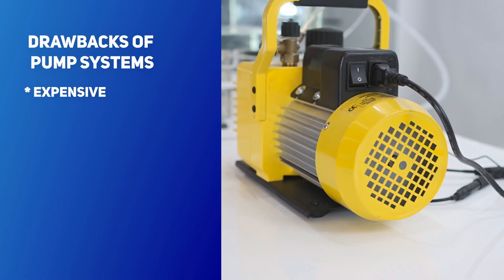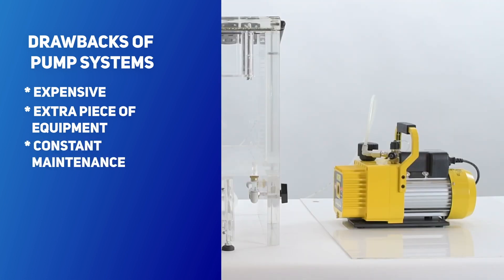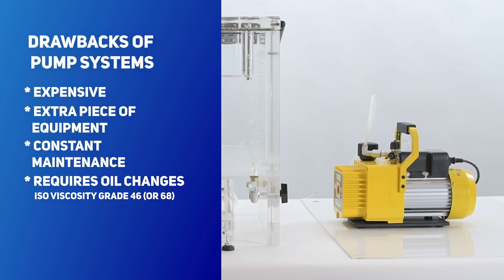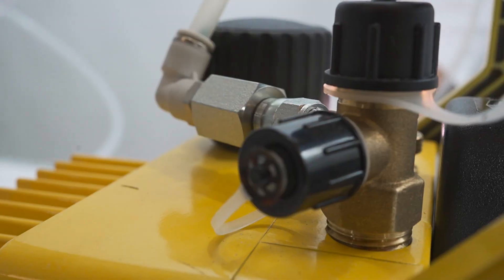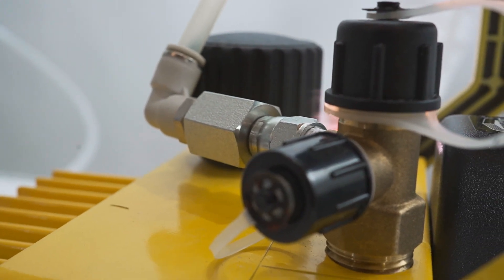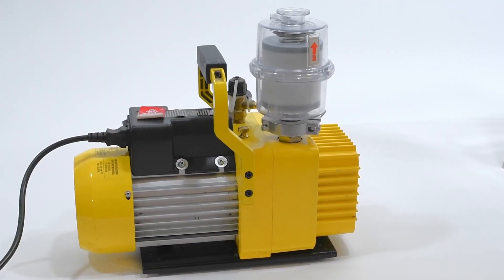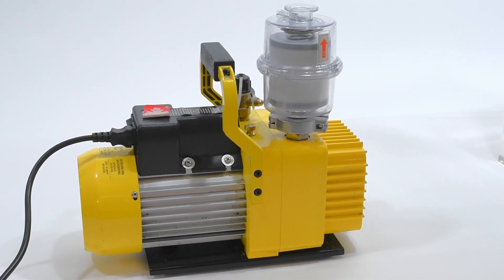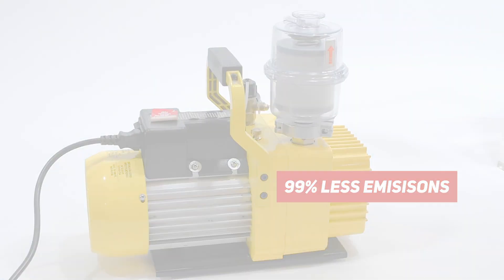Now let's explore the drawbacks of a traditional pump system, which is more expensive than the Venturi system. It takes up more space and needs regular maintenance. It works with a two-stage rotary vane, requiring oil, which must be changed depending on how often it's used, and tends to overheat if used over long periods of time or while running many consecutive tests. Lastly, traditional pumps can generate non-toxic fumes, making them unsuitable for sterile environments. For these applications, we offer an optional filter, reducing the pump's emissions by a remarkable 99% without compromising the pump's efficiency.